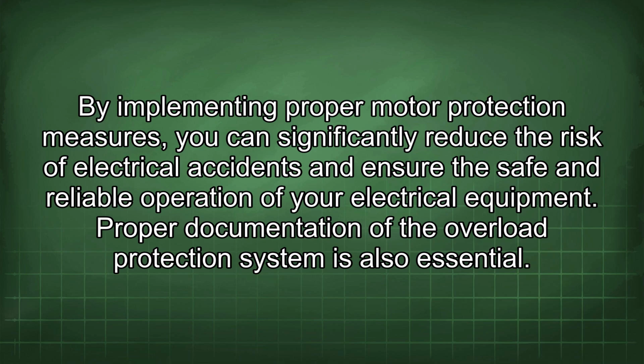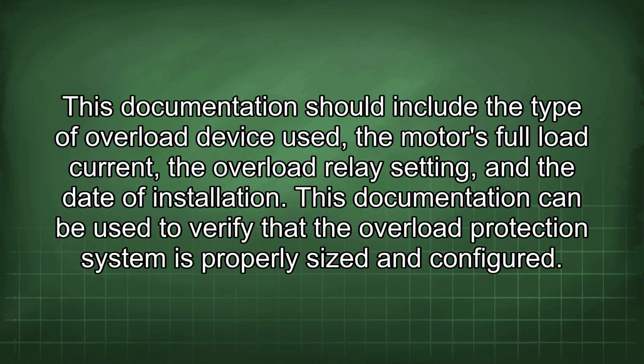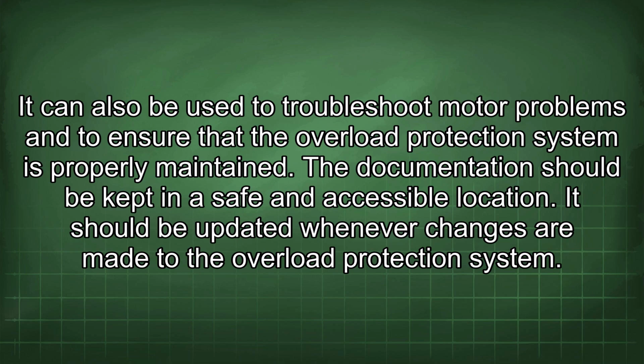Proper documentation of the overload protection system is also essential. This documentation should include the type of overload device used, the motor's full load current, the overload relay setting, and the date of installation. This documentation can be used to verify that the overload protection system is properly sized and configured. It can also be used to troubleshoot motor problems and to ensure that the overload protection system is properly maintained. The documentation should be kept in a safe and accessible location.